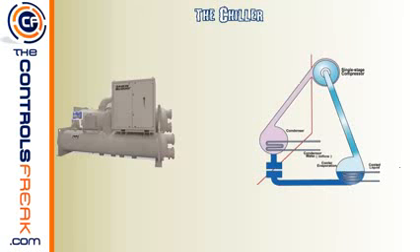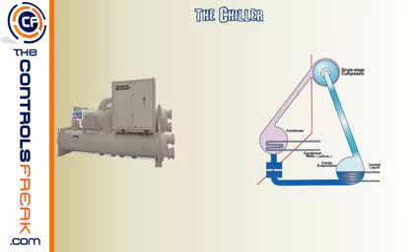Let me clarify on the evaporator and condenser sections. These lines represent water lines. On the condenser side, the water lines run to the cooling tower — this water helps cool the refrigeration cycle. Instead of using air like the condenser unit on the outside of your house, this uses water to cool that side of the chiller. On the evaporator side, water lines run into the building.